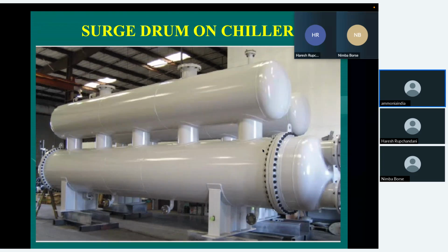Remember, liquid coming to the compressor is a general phenomenon. Liquid comes to the compressor in 4 different forms. One is liquid slug. That is, when you defrost the system, suddenly the liquid shock comes to the compressor. The second is continuous migration of liquid coming to the compressor, which was taking place in this particular case. The third is liquid droplets, small liquid droplets coming to the compressor. How can you make out liquid droplets? Because your valve plates, your piston rings, etc. will break if droplets are coming to the compressor.